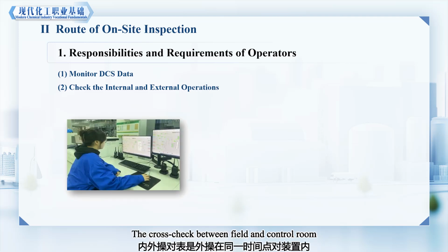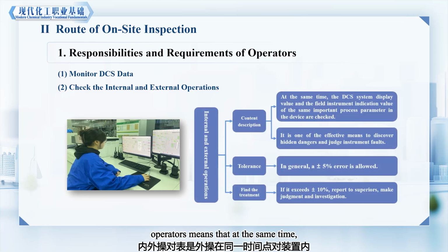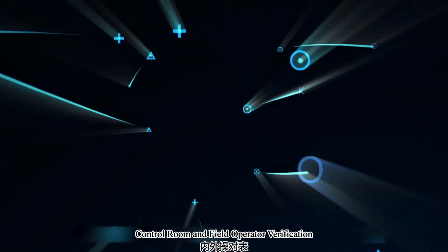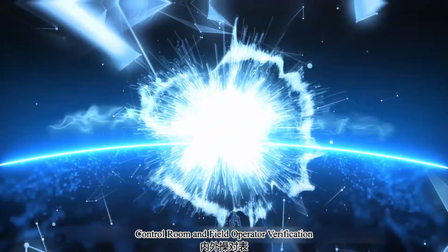The cross-check between field and control room operators means that at the same time, the field operator compares the DCS display value of an important process parameter with the on-site instrument reading. By comparing the results from these two different measurement methods for the same parameter, the accuracy and authenticity of the process parameter measurement are verified, which is one of the effective means to detect potential accidents and diagnose instrument failures. Control room and field operator verification.